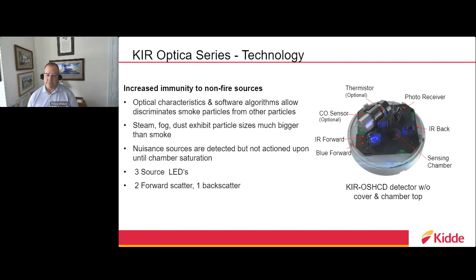Thanks, Mike. So just to expand a bit more on the technology—the device you see on the right is a device with the hood taken off. You'll see the item in the upper right corner labeled photo receiver. That's the traditional photoelectric principle of detection: particles come into the smoke chamber and break up the transmitting and receiving LEDs, which activates the alarm.